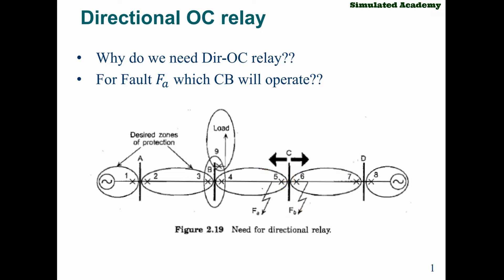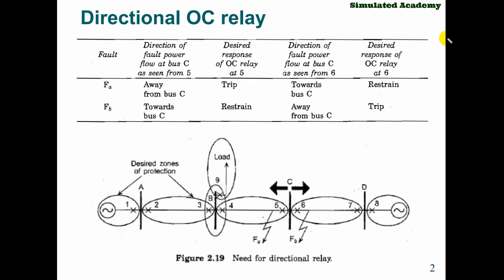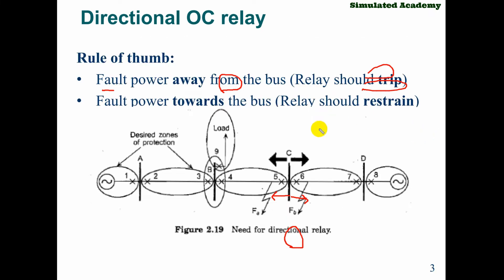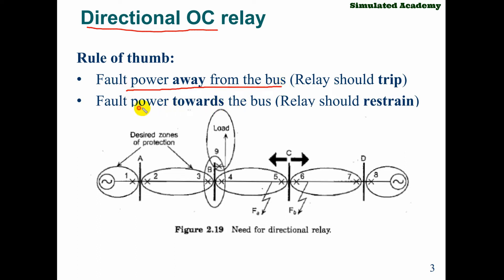So this is the thumb rule. If fault current is away from the bus, that relay operates — it should trip. Whichever relay has current towards the bus — for example relay 6 — it needs to restrain for fault Fa. Away from the bus — relay 5 — it must operate. Similarly for fault FB, away from the bus current causes operation; towards the bus means restrain.